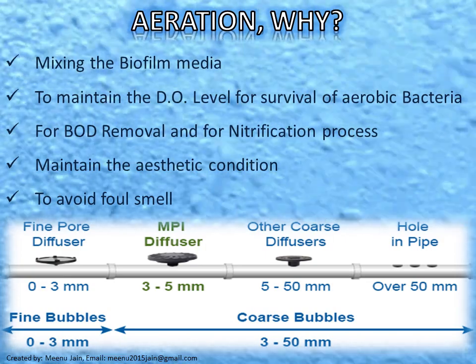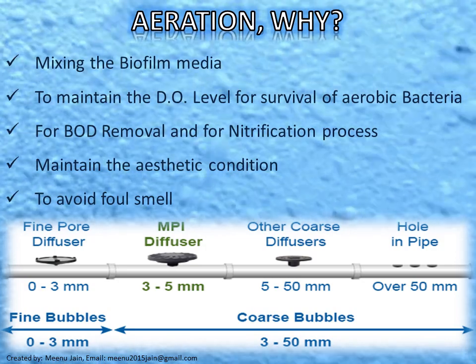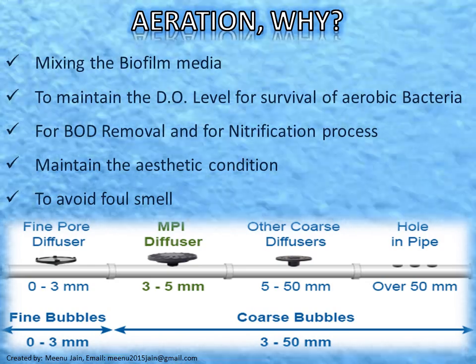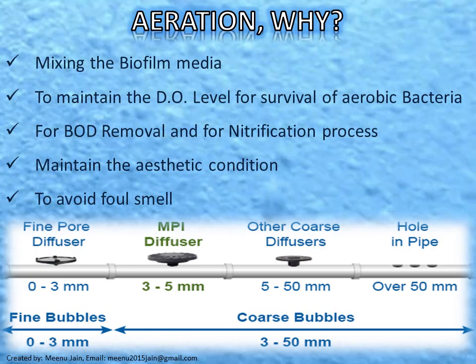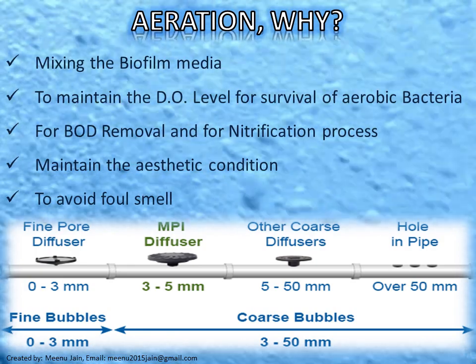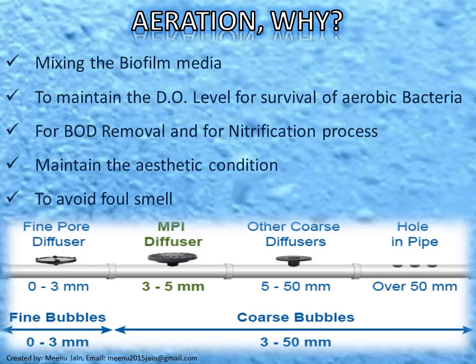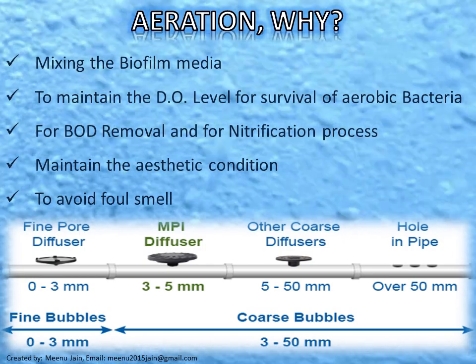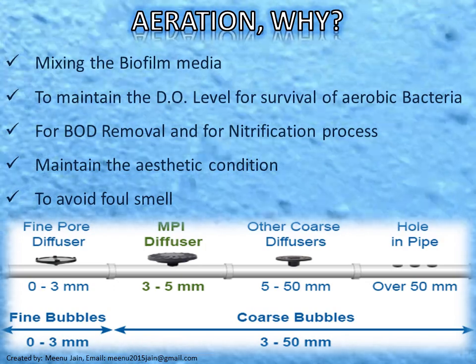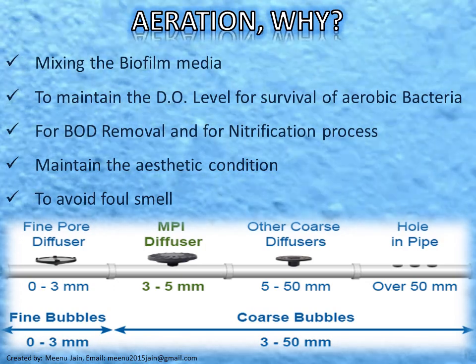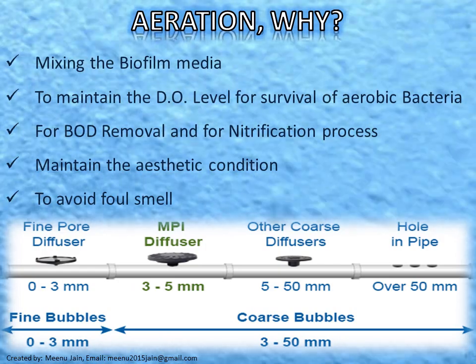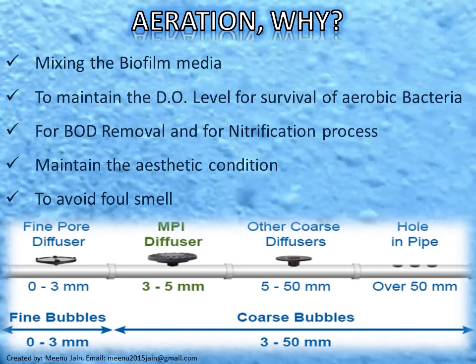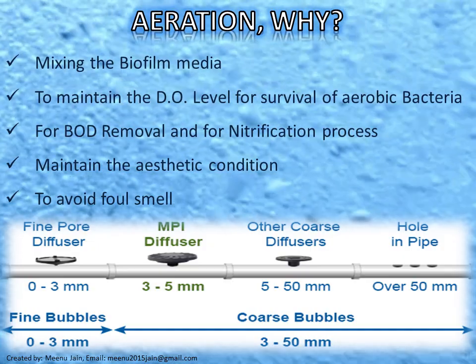The efficiency of oxygen transfer depends on many factors such as the type, size, and shape of the diffuser, the air flow rate, the depth of submergence, tank geometry including header and diffuser location, and wastewater characteristics. Typically, standard oxygen transfer efficiency increases with the depth of the MBBR tank, and 4.5 meters is generally considered the most common submergence depth for diffusers. Fine bubble diffusers have 0–3 mm bubble size, medium pore diffusers 3–5 mm, and coarse bubble diffusers 5–50 mm.